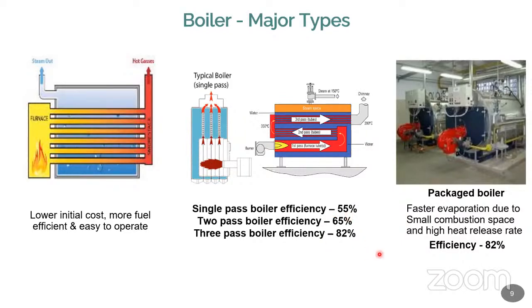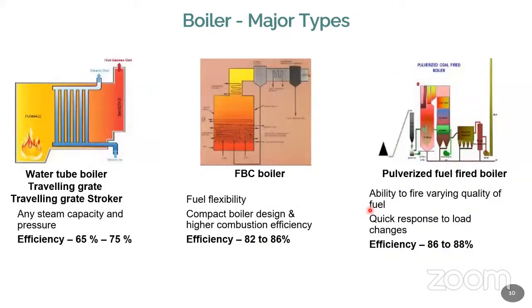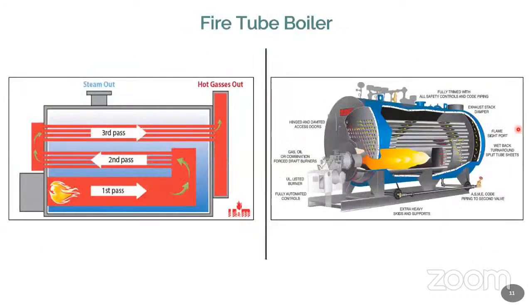So mostly in industry, we are using 3-pass boilers, having an efficiency of 82-85%. Apart from that, other boilers are available. That's called a traveling grate stoker boiler, which has an efficiency of 65-75%. Then we have fluidized bed combustion boilers, FBC boilers, which have an efficiency of 82-86%, which is normally higher. Pulverized fuel boilers, now this is a very good one, having a higher efficiency of more than 85%.